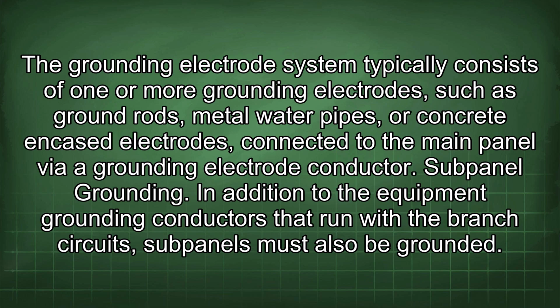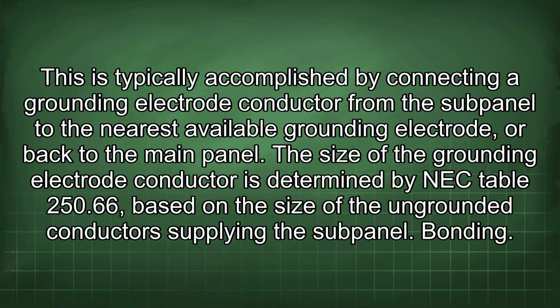Subpanel grounding. In addition to the equipment grounding conductors that run with the branch circuits, subpanels must also be grounded. This is typically accomplished by connecting a grounding electrode conductor from the subpanel to the nearest available grounding electrode, or back to the main panel. The size of the grounding electrode conductor is determined by NEC Table 250.66 based on the size of the ungrounded conductors supplying the subpanel.